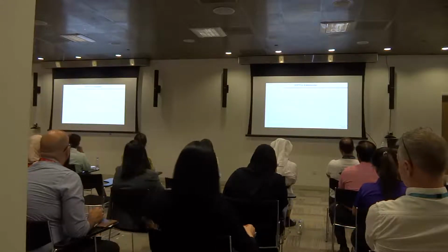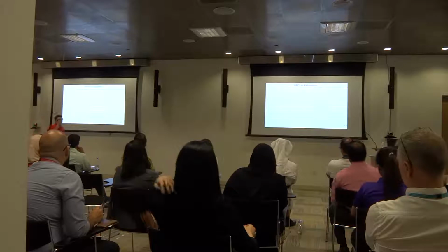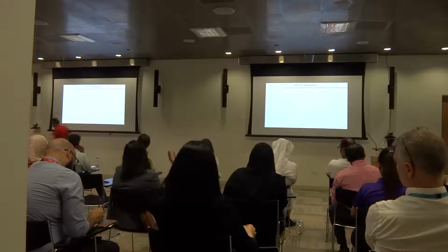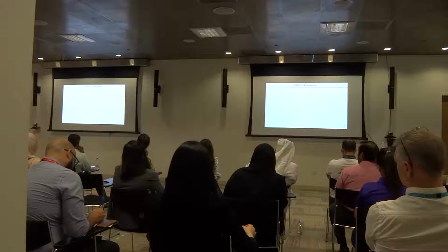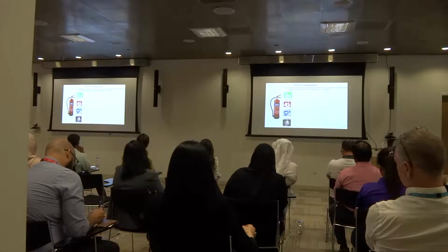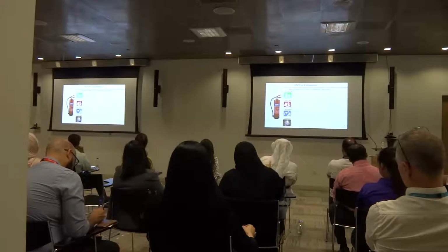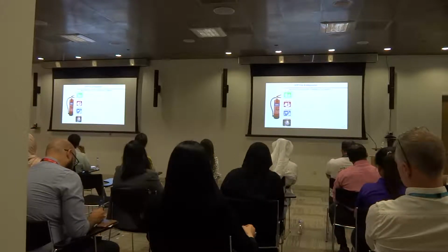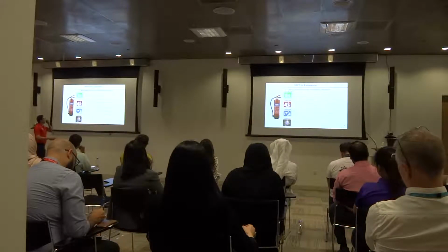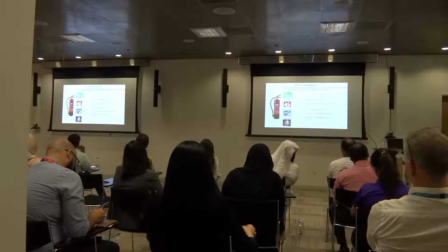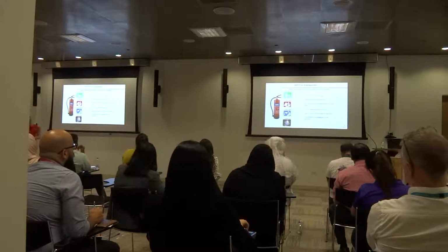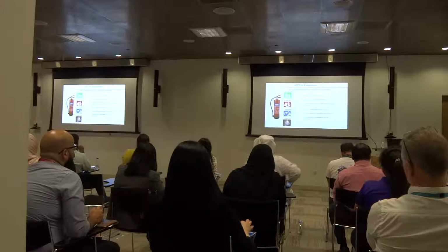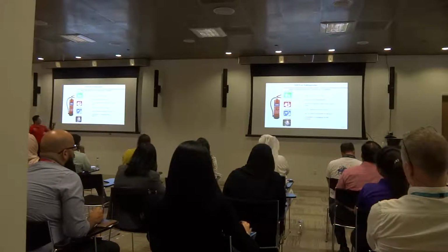DCP fire extinguisher. Do you know what DCP extinguishers mean? Dry chemical powder. It is safe to use for Class A ordinary combustible material, Class B liquids, electrical equipment, and even combustible metals. It has 8 to 25 seconds discharge time, has a pressure gauge to allow visual capacity check, 5 to 20 feet maximum effective range, can be started and stopped as necessary, and extinguishes by smothering burning materials.